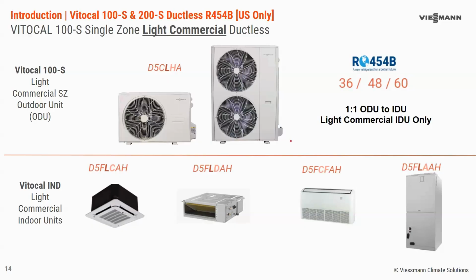The light commercial units have a separate communication wire compared to the residential ductless. So you just need to make sure that you're choosing the right indoor unit for your outdoor unit, which is all listed in the documentation, as well as our compatibility matrix. But that's just something to call out. The light commercial outdoor units need to be with the light commercial indoor units, and there is a more limited selection of indoor units that are for light commercial.